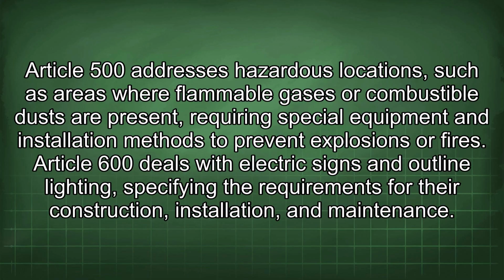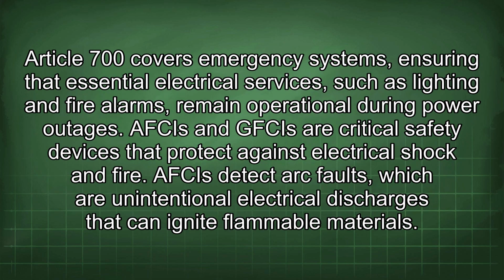Article 500 addresses hazardous locations, such as areas where flammable gases or combustible dusts are present, requiring special equipment and installation methods to prevent explosions or fires. Article 600 deals with electric signs and outline lighting, specifying the requirements for their construction, installation, and maintenance. Article 700 covers emergency systems, ensuring that essential electrical services such as lighting and fire alarms remain operational during power outages.